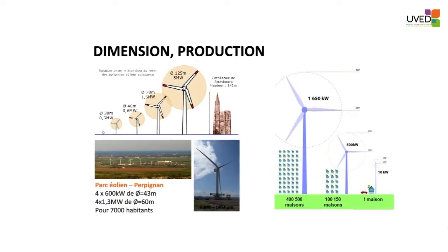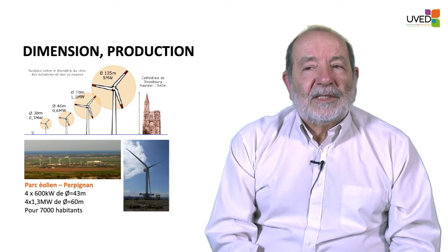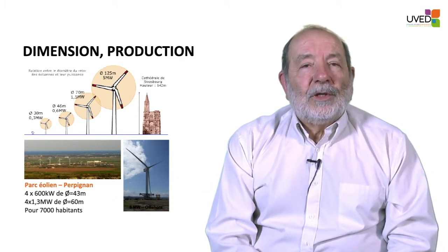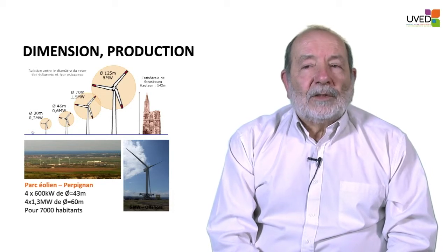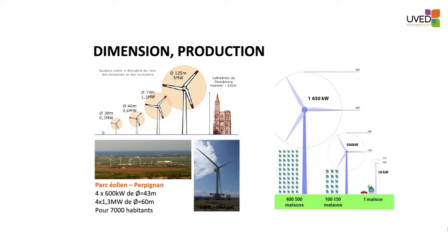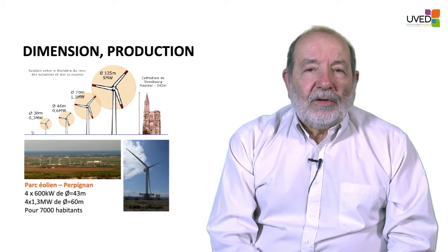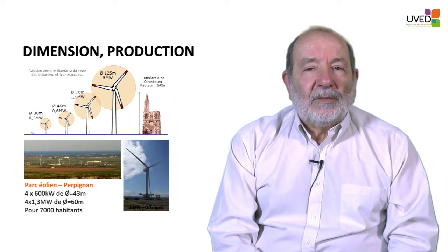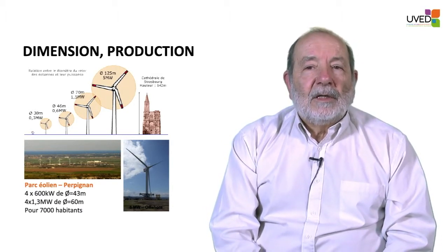With a rotor of 30 meters, we can achieve a power of 0.3 megawatts. As we increase the rotor area — from 46 up to 125 meters — the power increases accordingly. With a 125-meter rotor, the generator will release 5 megawatts, and the nacelle will be more than 150 meters above ground. For example, four windmills of 600 kilowatts and four of 1.3 megawatts is enough to supply power to a small town of 7,000 inhabitants.